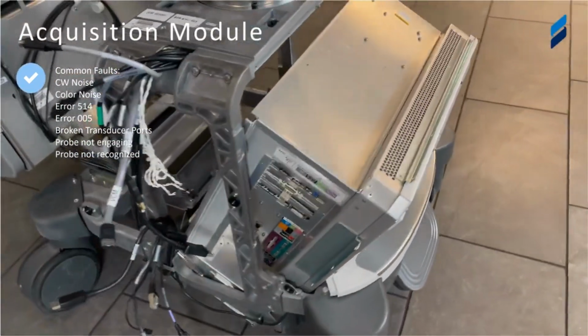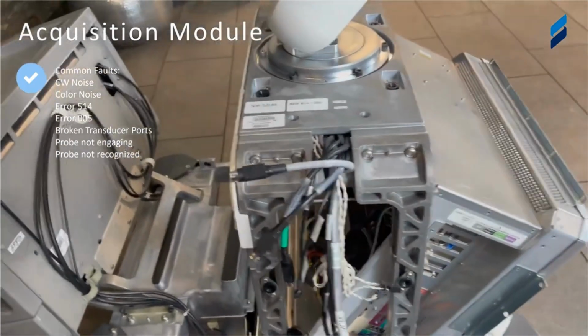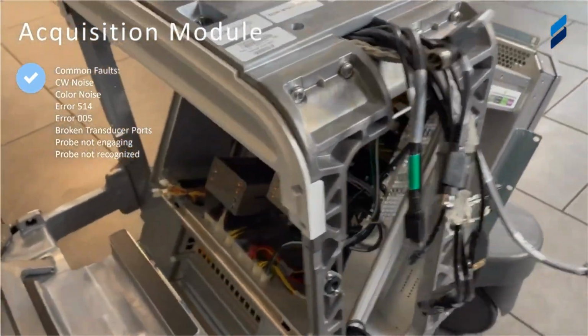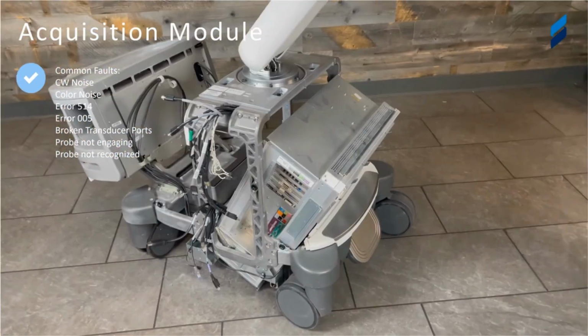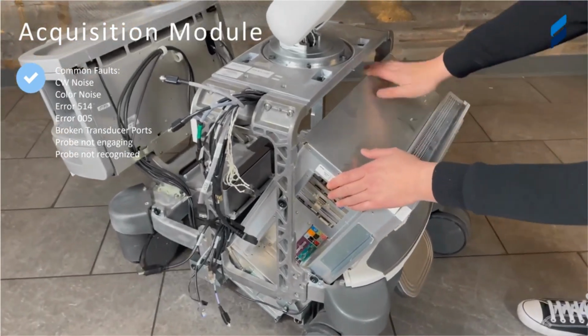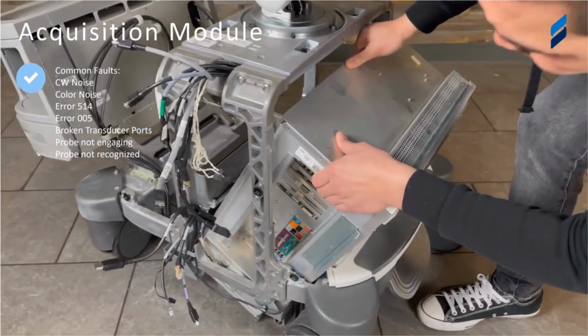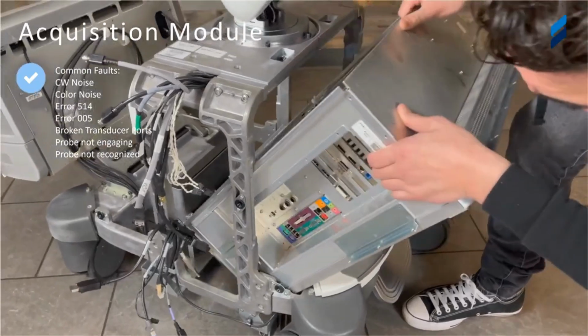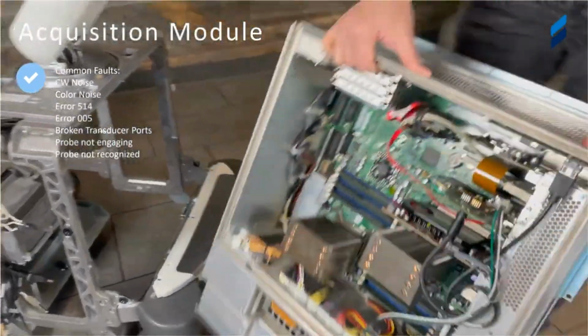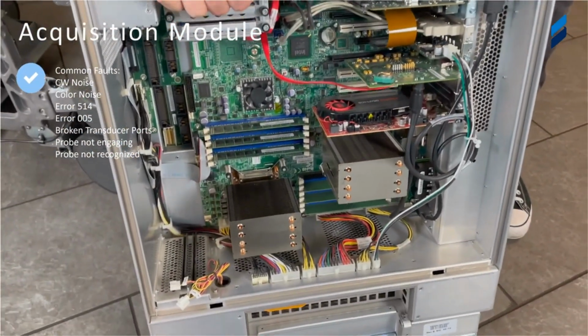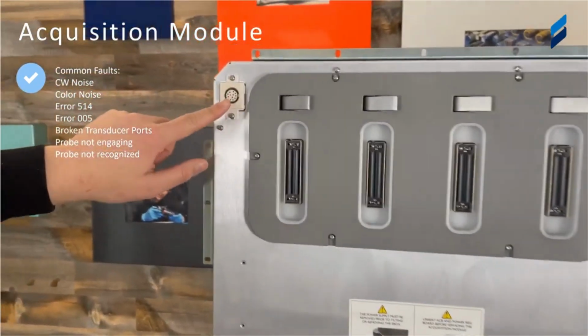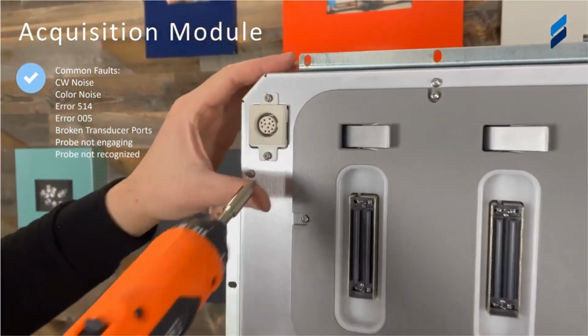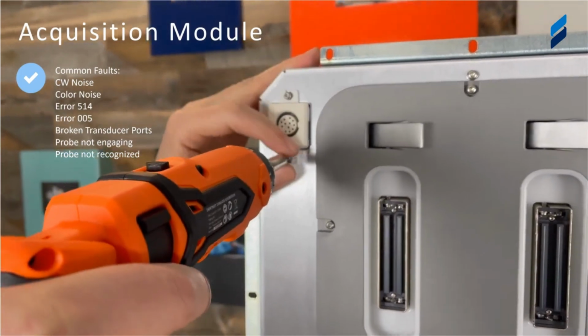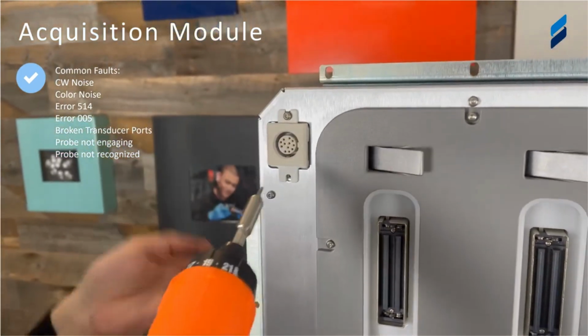As you can see, with all the cables removed and the power module in the back removed, that allows the assembly to fall forward. If you don't go through that process, if you keep trying to tilt the assembly, it will start tugging on the cables and start breaking things. All right, get a good grip on it. It's not light, not heavy, and now you have this assembly removed.